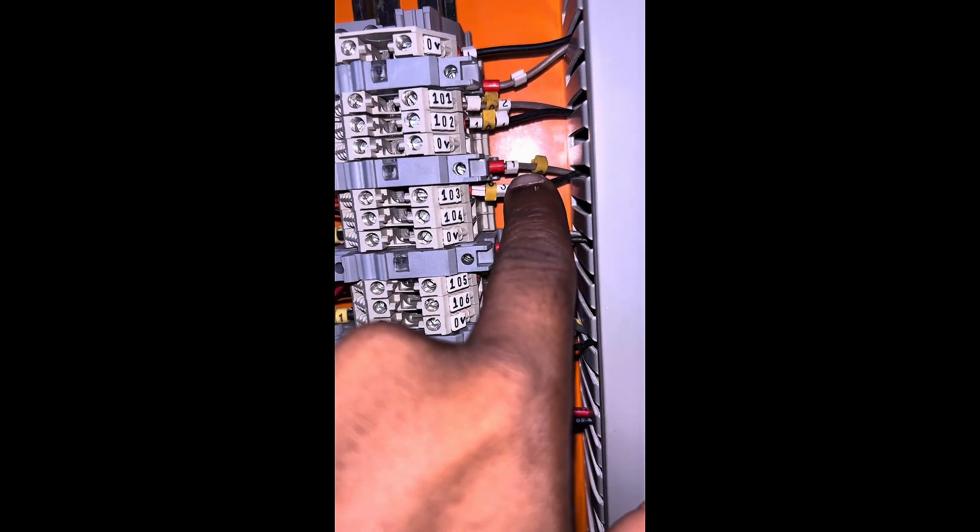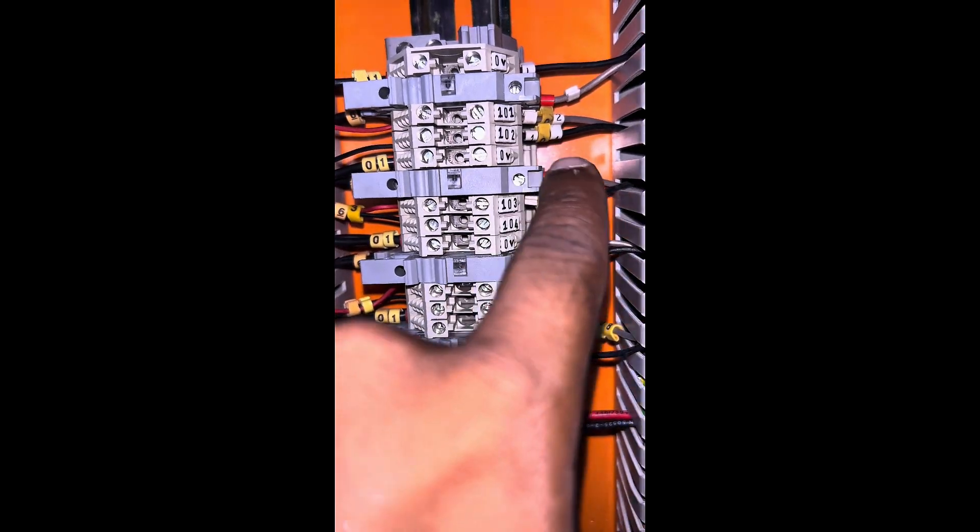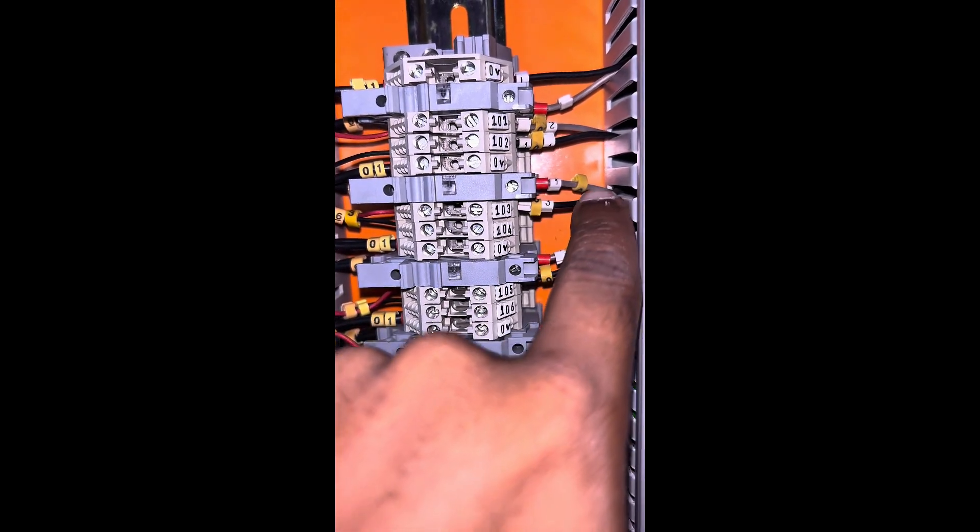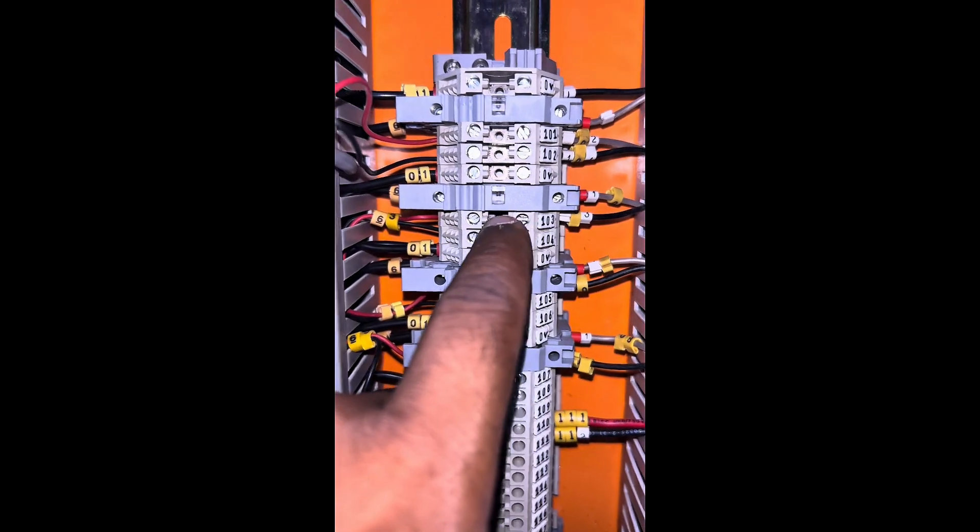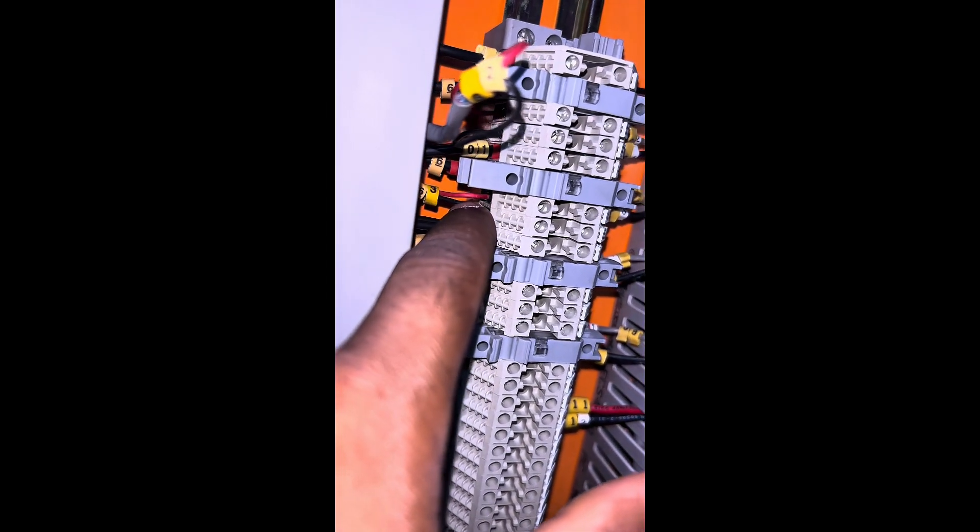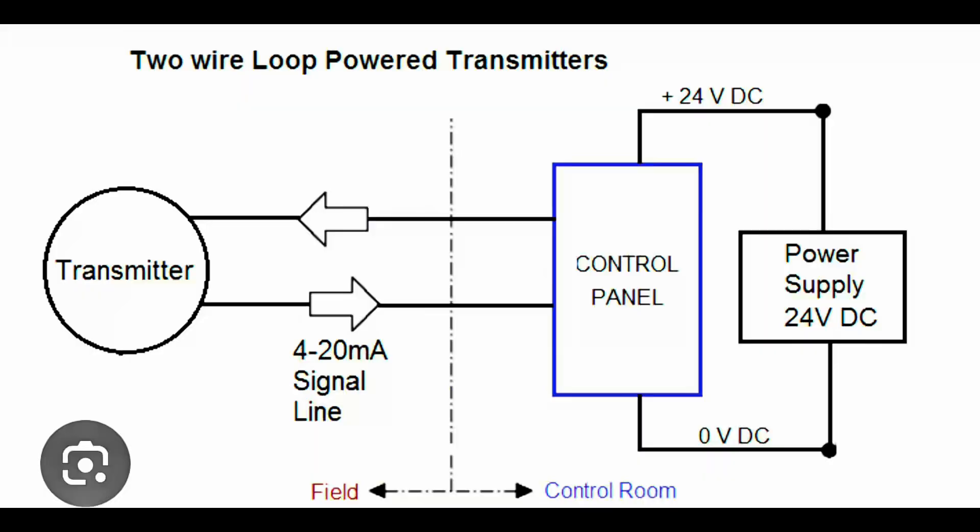From the terminal you can see this is the 24V supply going to the water level sensor. From the fuse carrier out, it is going to the water level sensor 24V. The cable below the 24V is the return cable that we are using to measure the 4-20mA.